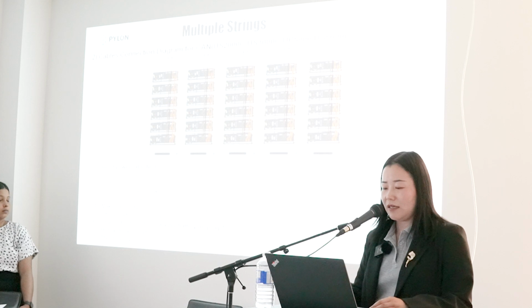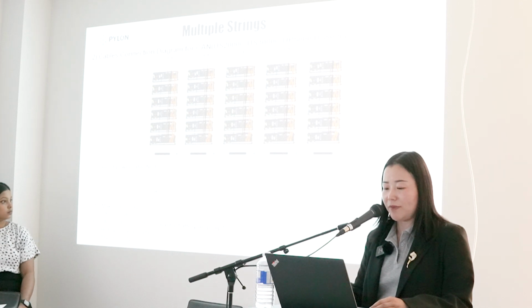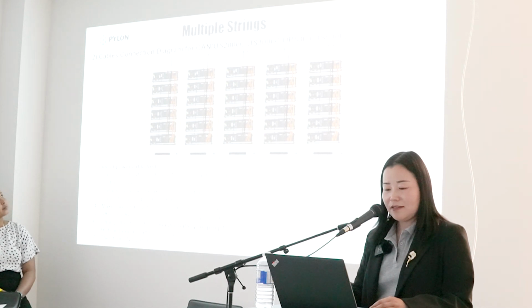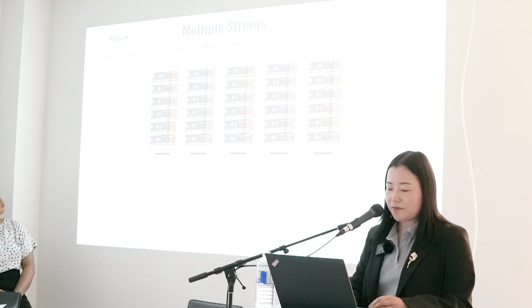After finishing the communication cable connection, follow the product manual of the battery to connect the battery power cables in parallel. Each pair of cables holds a max of 100 amp constant current. Connect enough pairs of cables based on the calculation of system current. Secondly, a suitable protection breaker between the battery system and the inverter is required. Thirdly, connect the power cable of the LV hub.